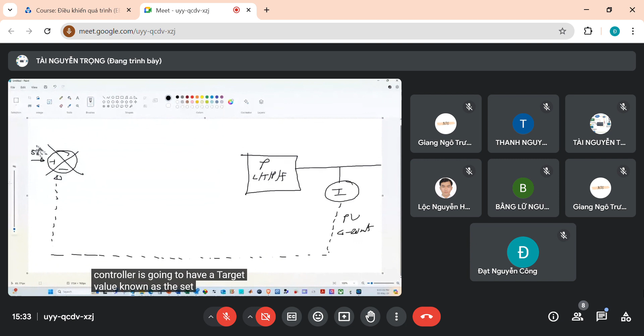Now, have a look at what I'm going to go and do. My controller is going to, in this case, be negative feedback, a closed loop control. My controller is going to have a target value known as the set point. And it will compare the process variable to the set point. And if there's a difference, it's going to calculate it as the error. The error is the process variable minus the set point for a direct acting controller, or the error is going to be set point minus the process variable for the other control that we are going to go and have. So it's going to come in that respect.